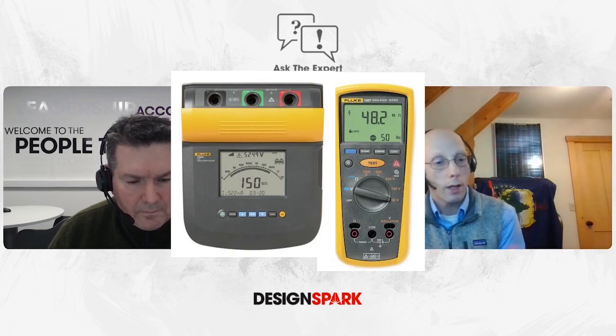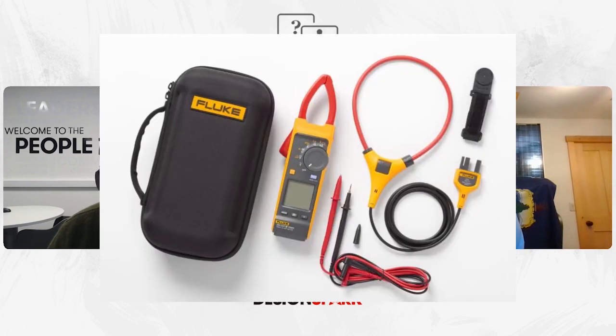We have current clamps that we use to detect current, and we can see if current is out of the normal parameters. We have a solar-specific current clamp at Fluke, the 393 meter. It has a 1500 volt rating, which has become a more common voltage on the DC side on utility scale projects. It also has a high category rating, so it has a high safety rating when we're working with these types of arrays.